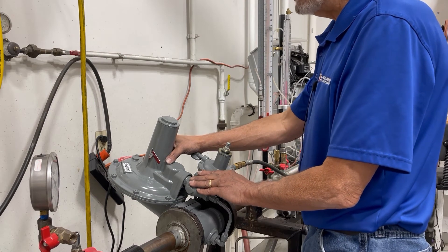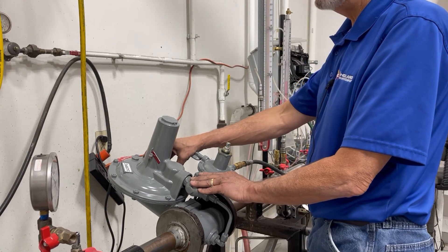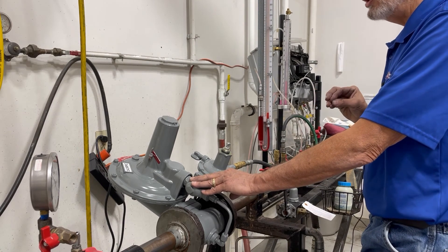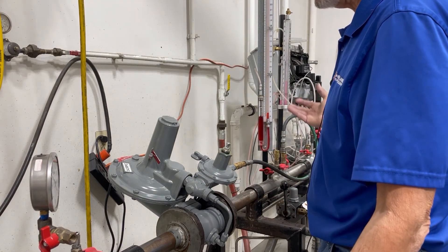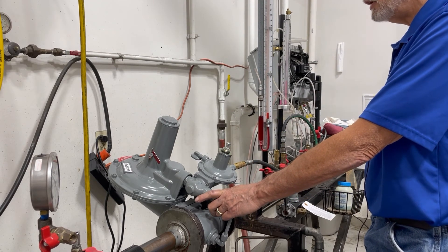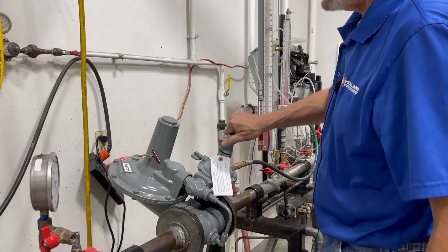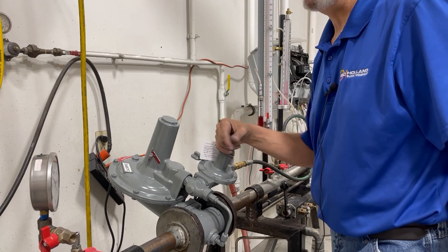If you try to do that too quickly you are going to bend the diaphragm that is in the main regulator and you will have problems with regulation from there on. So make sure that you energize this regulator very very slowly. At this point, once you have your downstream pressure regulated the way you want it and you have reached that pressure, you can go ahead and reinstall your top cap. And that is the demonstration for an RPC change of regulator pressure.